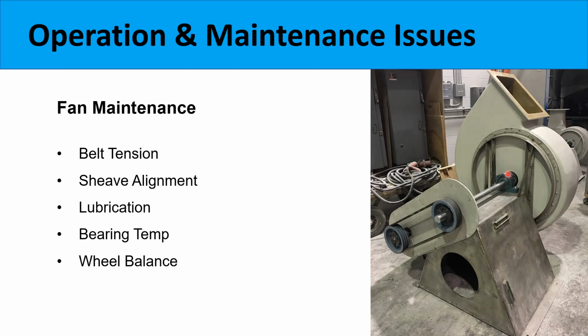Each bearing manufacturer has their own recommended lubrication guidelines, and it can be a bad thing to over lubricate a bearing. So sometimes too much lubrication can be a bad thing for a set of bearings, depending on that style. So certainly follow the directions of that particular manufacturer. Also, it's important to make sure these sheaves are lined up. If they're not lined up properly in alignment with each other, then they can cause excessive tension and wear on those belts and premature failure.